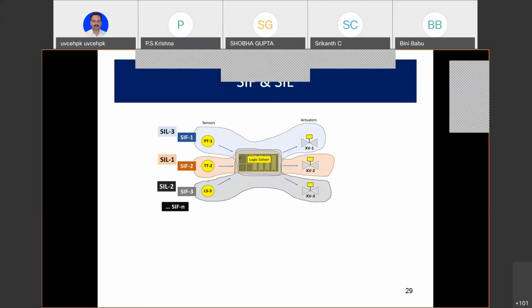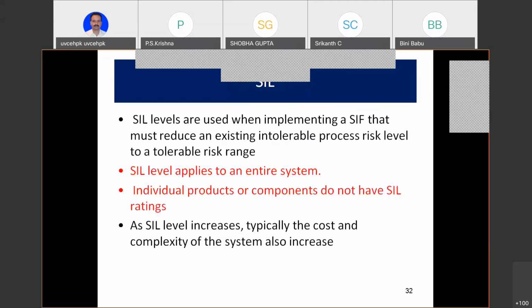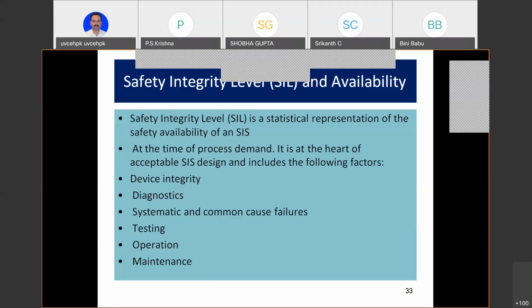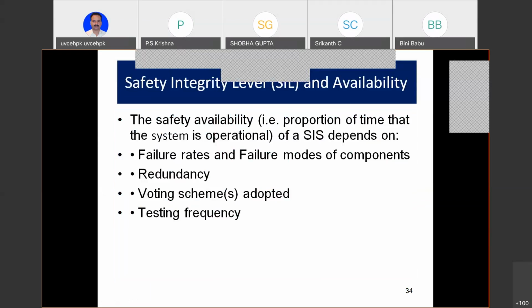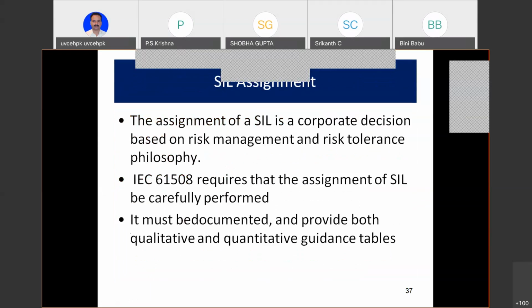No. That's the most important thing, and I have mentioned that and also underlined it. So SIL 3 is your factor which tells you, yes, I'm very reliable, I'll work whenever you want. It actually gives you the safety performance of the complete system because of its presence. SIL level applies to an entire system. Individual products or components do not have SIL ratings. What you can say is that your pressure switch or transmitter is capable of operating in a SIL 3 environment. Now, we will go into a little more detail and see this slide, and then I want you to see this one.